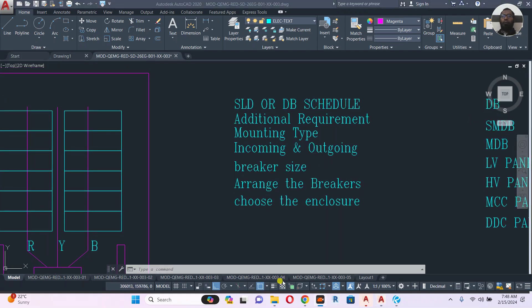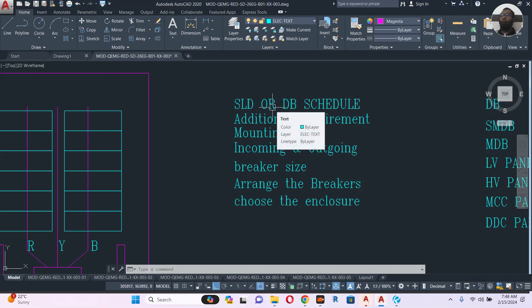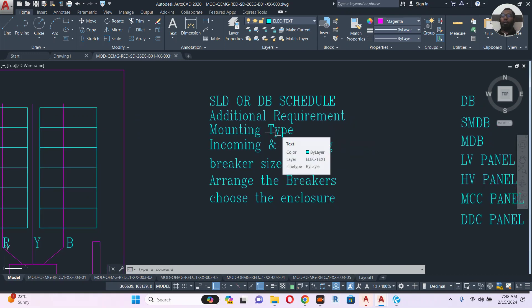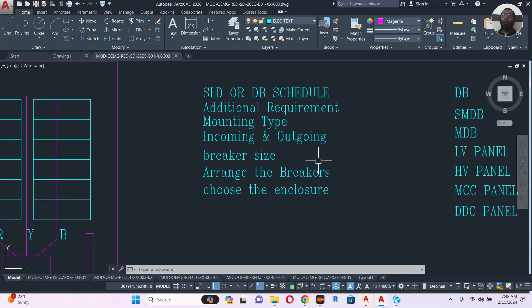So what are the requirements to design a panel? First, you need a correct, updated, and validated single line diagram or DB schedule. Second, you need to know any additional requirements — such as shunt trip, fire alarm connection, etc. Third, you need to know the mounting type: flush mounted or wall mounted. Then check the incoming and outgoing cables from the SLD, and decide the panel entry — top or bottom entry.